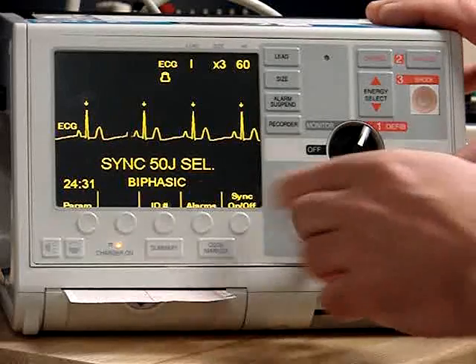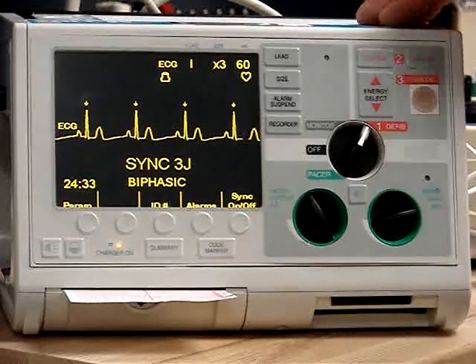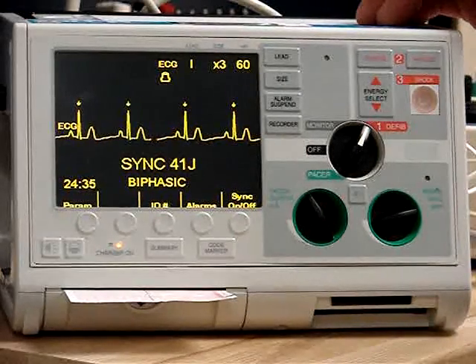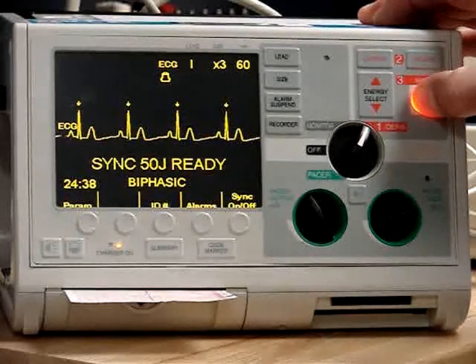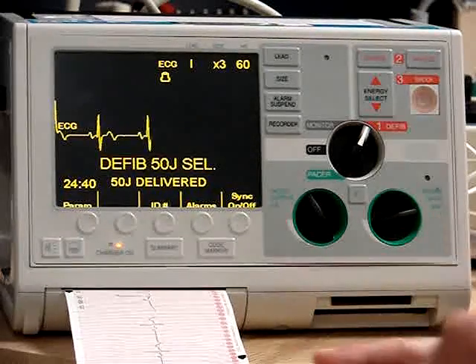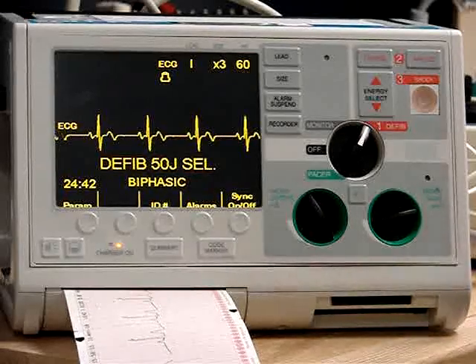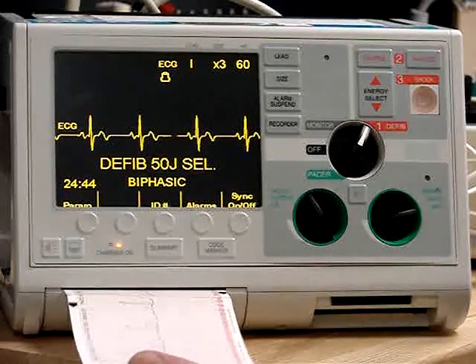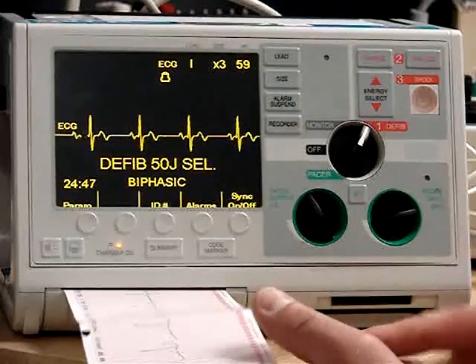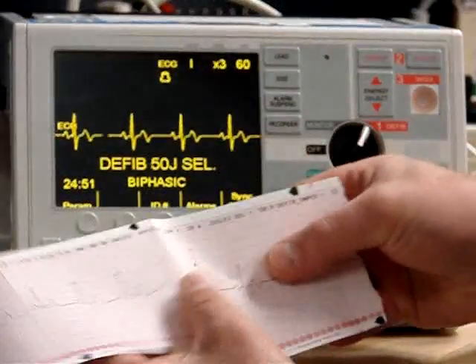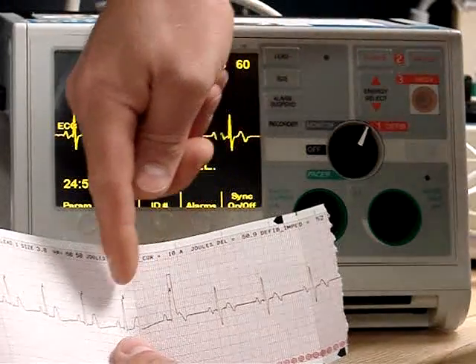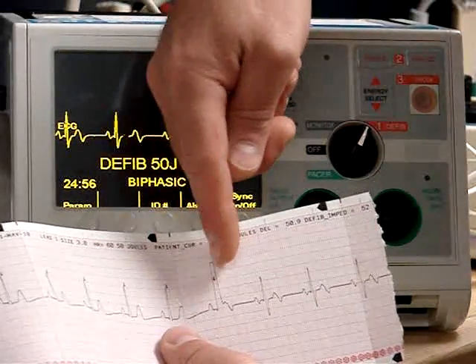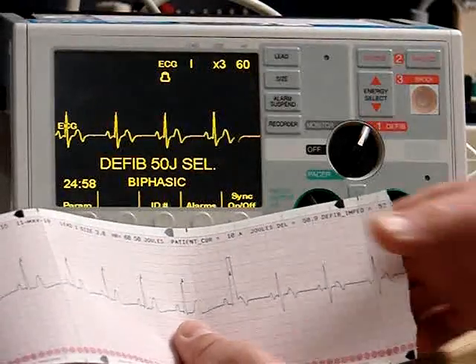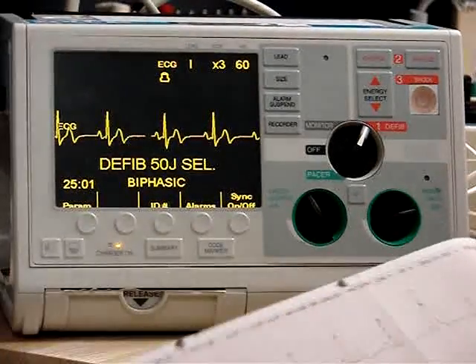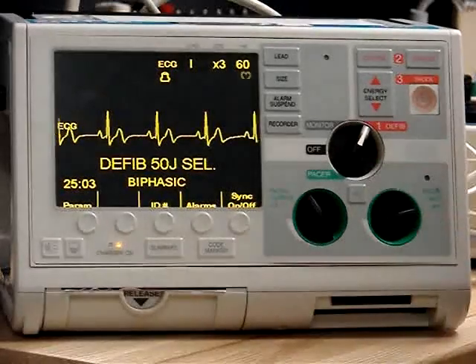So our synchronizer's on, we're set to 50 joules, charge, push, and it discharged. Now to make sure that it discharged at the same time in sequence with an R wave, the recorder will spit out a wave, and we can see when it discharged, and we can see that it is in sequence with an R wave. So the synchronizer function and the recorder function is operating properly.